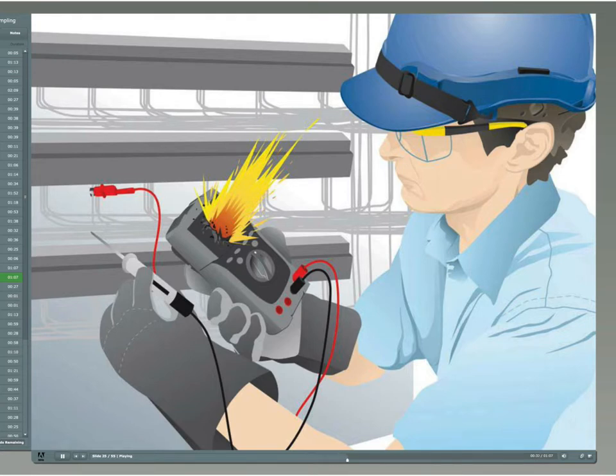When this happens, an arc will form across the open part of the circuit. If it is not immediately controlled, the arc will cause the air in the vicinity to become superheated and convert into plasma, which is conductive, and allow even more current to flow through the air. This is called arc flash. In extreme cases, it releases the same amount of energy as a few sticks of dynamite. An arc flash victim may suffer fatal burn injuries from the fierce heat. Could this happen? Absolutely.